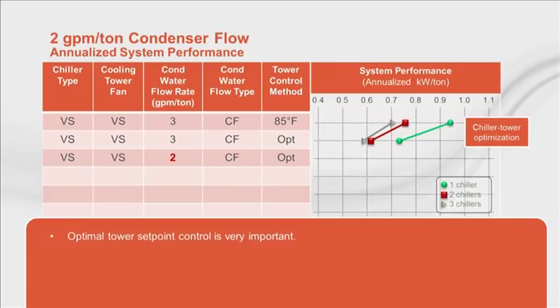What if we change the condenser design water flow rate? Since we're interested in the highest system performance, when we reduced the condenser water flow rate, we left the pipe sizes the same and used the same cooling tower fan. Reducing the water flow rate reduces condenser water pump power and energy and gives us a better, closer cooling tower approach temperature. The towers are more effective when given warmer water.